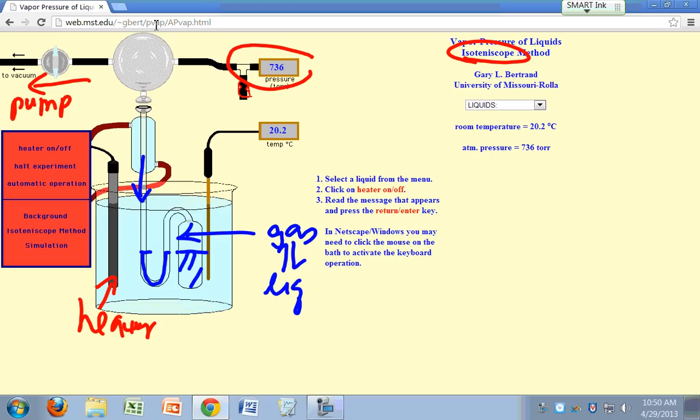First thing you need to do is heat this up so that you can get rid of any air bubbles that you may have in there. Any air that's in your system you'll need to bubble out. So the only thing you'll have in there is pure vapor of whatever liquid you're putting in.